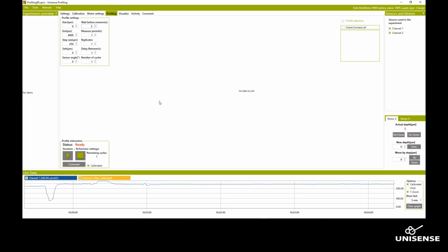Then we need to find where to start the profile. And now, because of this very murky sediment or plexiglass tube, I can't really see where the sensor is. So now I'll go to the motor control here for the depth axis. The actual depth is 0. Then I can set either a new depth and click go to, or I can set a step. I would normally set a step of 1 millimeter here because I think I'm just a few millimeters away from the sediment surface. And then I'll click down. And then I will follow the concentration down in the live view to see. It didn't change this time. Let's try again. When I get close to the sediment surface or the diffusion boundary layer, the concentration will decrease, and I know then I'm close to the sediment surface. May need to go a few millimeters more. Still no change.